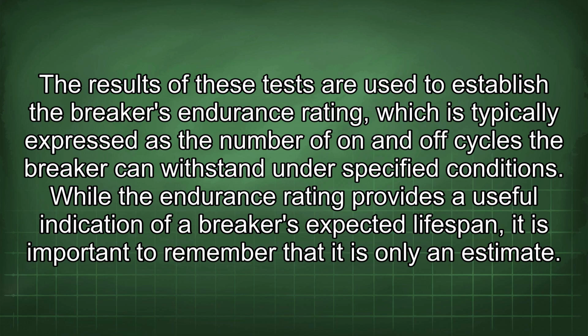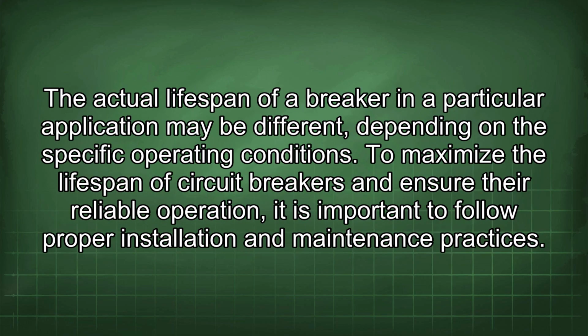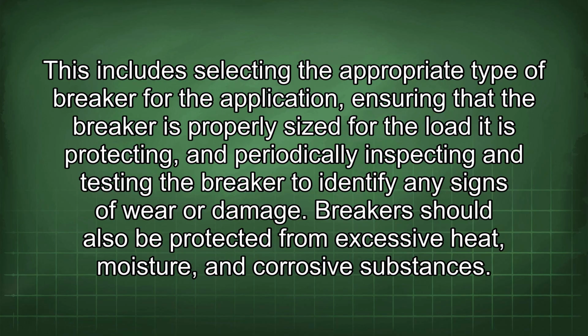While the endurance rating provides a useful indication of a breaker's expected lifespan, it is important to remember that it is only an estimate. The actual lifespan of a breaker in a particular application may be different depending on the specific operating conditions. To maximize the lifespan of circuit breakers and ensure their reliable operation, it is important to follow proper installation and maintenance practices. This includes selecting the appropriate type of breaker for the application, ensuring that the breaker is properly sized for the load it is protecting, and periodically inspecting and testing the breaker to identify any signs of wear or damage.